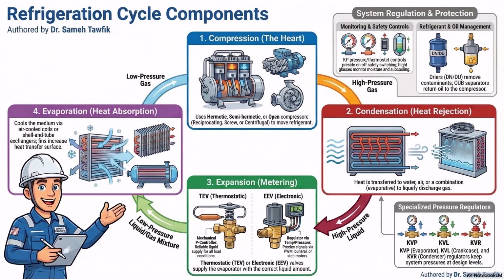And here's a kicker. Ice is an insulator. Wow. So the ice actually creates a thermal blanket over the metal. Exactly. It completely prevents the heat in the room from reaching the cold metal of the evaporator. That's wild. So, paradoxically, if you let your cooling coils get too icy, they entirely stop cooling the room. The system has to periodically pause, melt that ice off, and start again just to remain efficient.